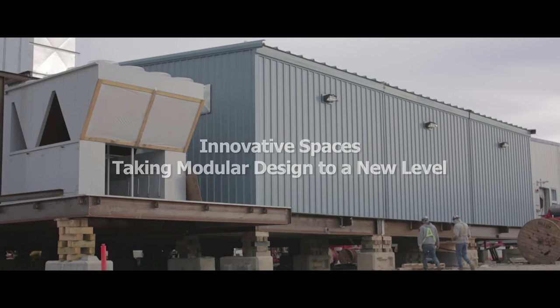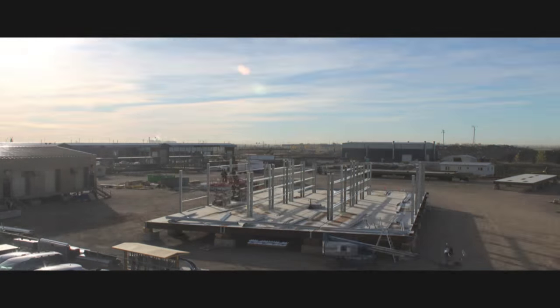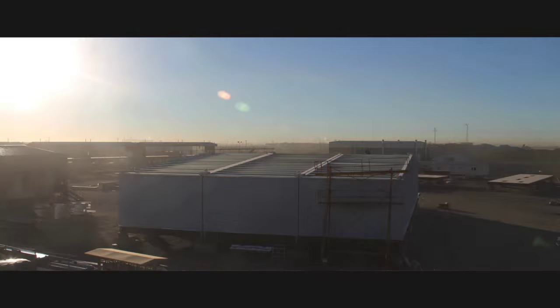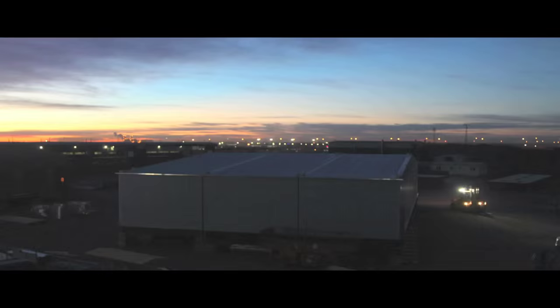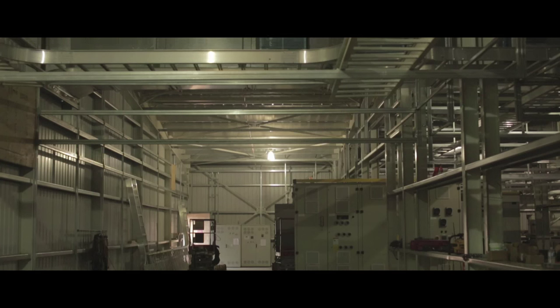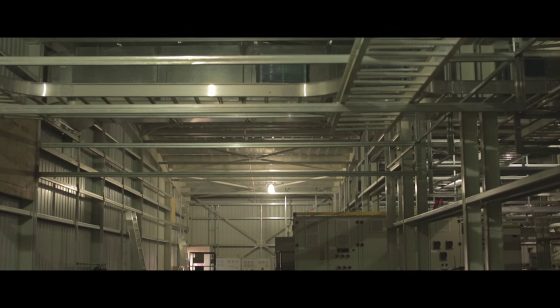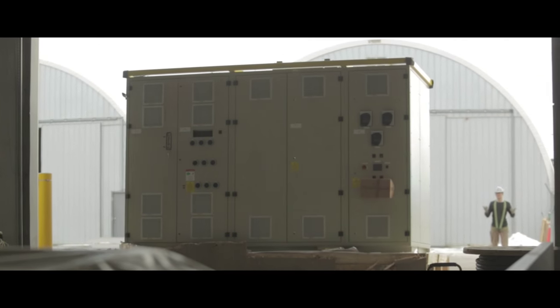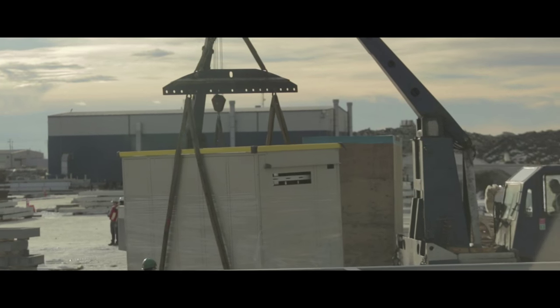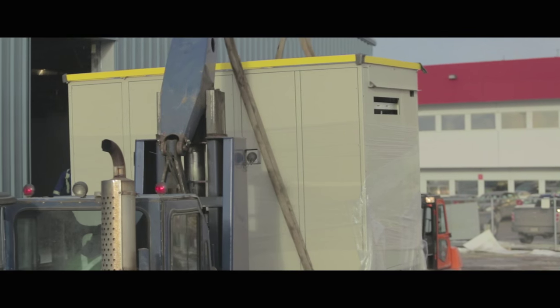This project is unique because of the three mods going together, which was 120 feet by 72 feet, so we've got over 8,000 square feet of wide open space — unique to a modular building because usually inside the building there are columns to support the roof. The client needed the clear span because of the size and amount of equipment they have. There are certain tolerances by building codes and electrical codes, and because there's so much congestion of large equipment — there were VFDs well over 35,000 pounds per unit — the space needed had no room for a column.